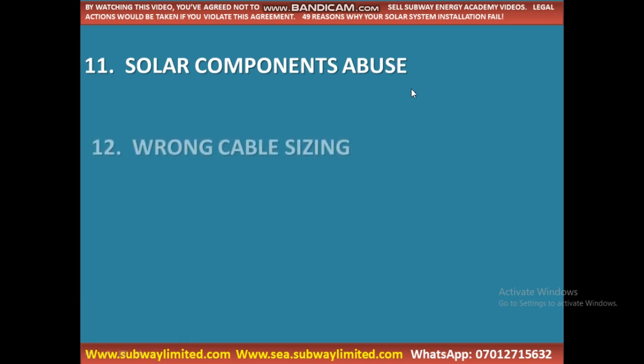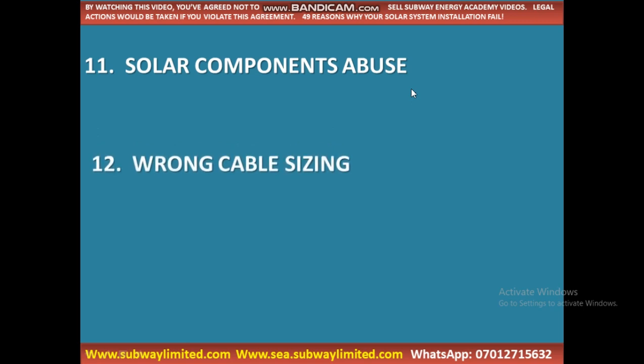Another thing that contributes to solar system failure is wrong cable sizing. Cable sizing has been a very big challenge in the solar industry, with voltage drop and other issues. We will talk about cable sizing in detail, but know that how you size your cable can affect the performance of your solar system. It might not allow your panel to deliver the needed power, or allow your battery to be properly charged. So there are many reasons why you need to understand how to professionally size solar cable.